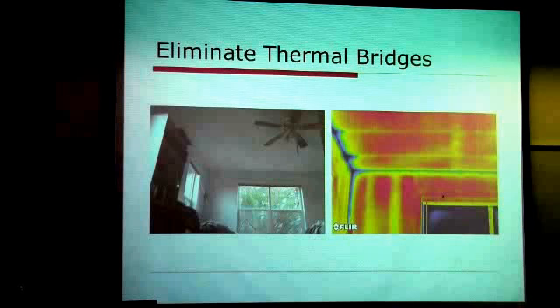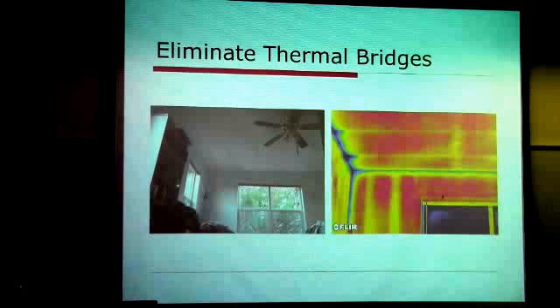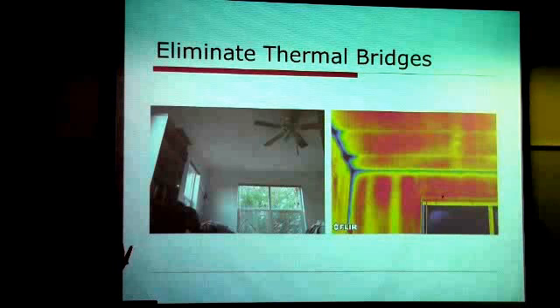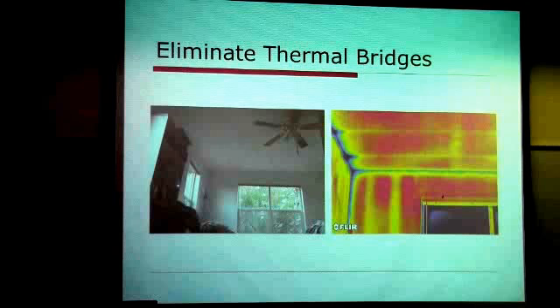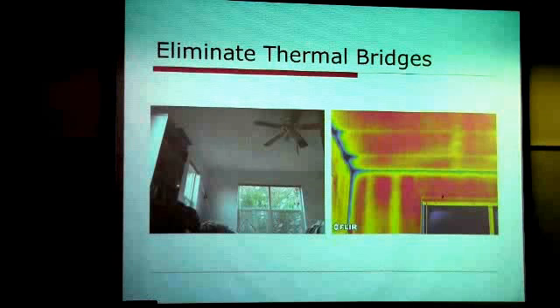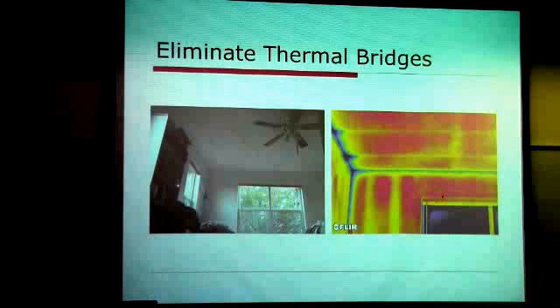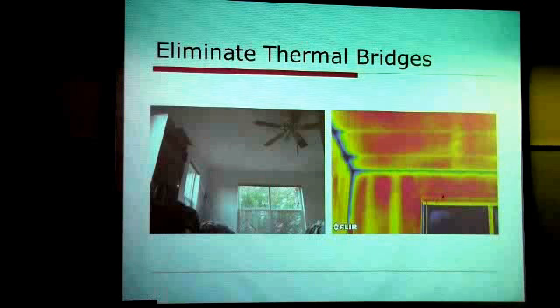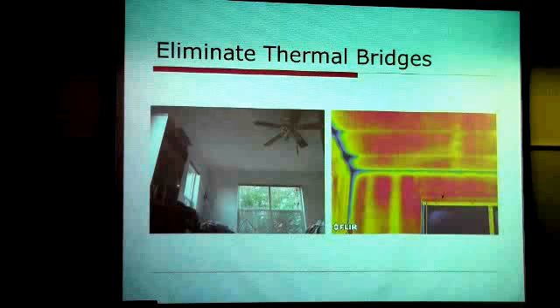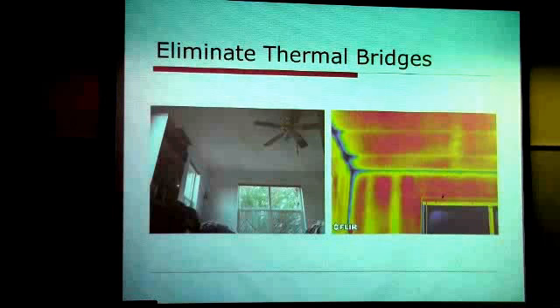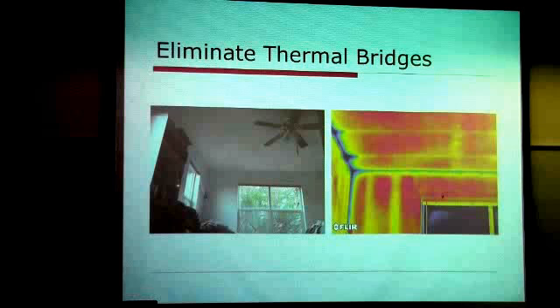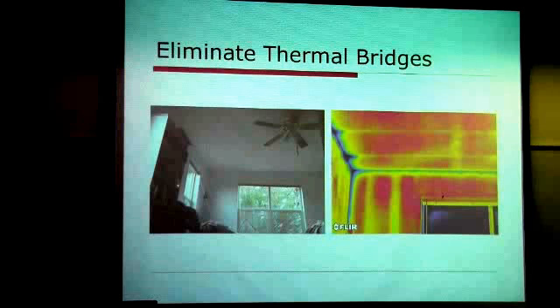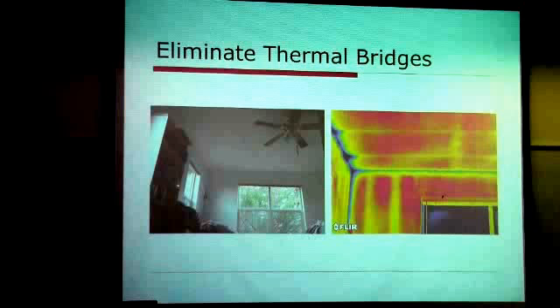But that's the main thing. Actually when you're using the bathroom and heating and taking a shower, all that air is going back to the HRV on a continuous basis, and it's capturing that heat and putting it into the incoming air. So the air streams never mix. One just gives off the heat to the other. So you're getting a constant supply of fresh air. We usually try to get about a third of an air change an hour, which is more than a lot of houses get, but it's fresh and heated, so you're not having to reheat it. And it's within 2 to 3 degrees of room temperature.